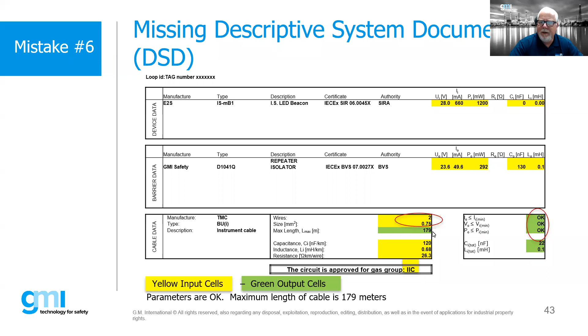So if we actually create our descriptive system document, this is what it would look like. We have our area classification, our non-hazardous area, this model number, our input parameters, our output parameters, and this information telling us that our maximum cable length cannot be any longer than 179 meters. We can use this DSD for every circuit that has this type of device.